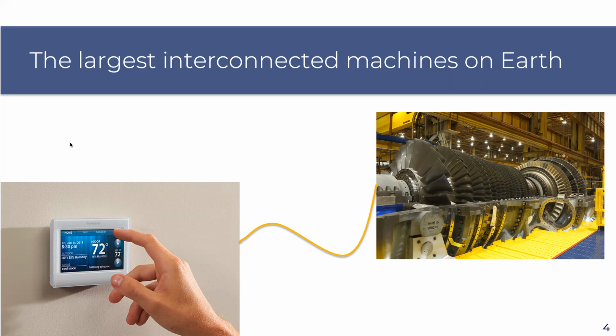This means that when you turn your thermostat up, somewhere out there in the grid, a gas turbine, a hydro turbine, or a wind farm speeds up a little bit, and when you turn it off, it slows down a little bit. We're trying to keep all of that in sync, so that every generator and every electric motor connected to the system, whether in a fan or the one cooling this projector, are all moving in phase, lined up within a very narrow tolerance of the same 60 hertz rotating frequency.